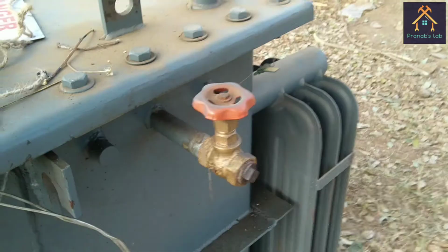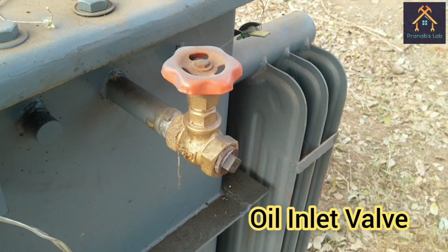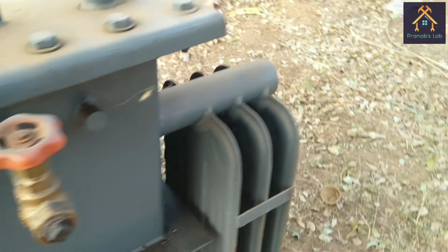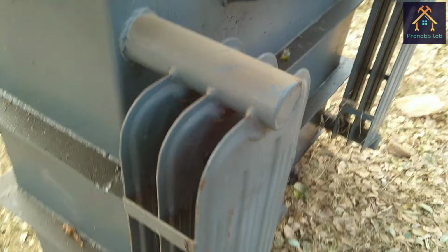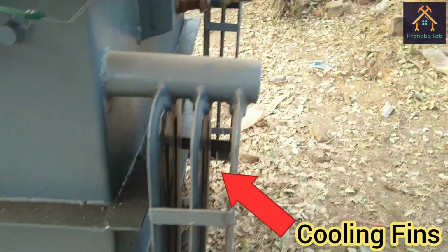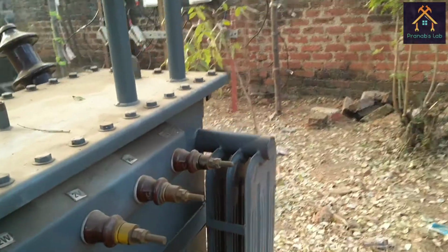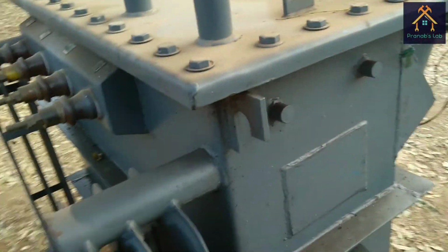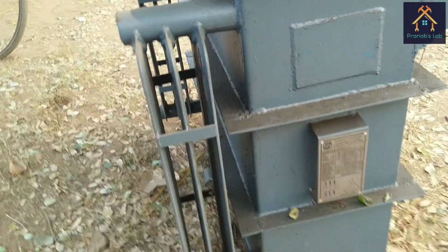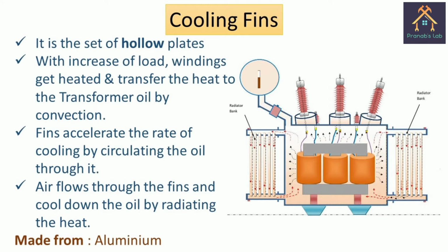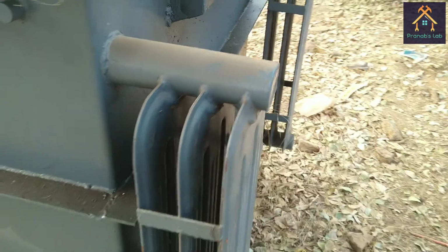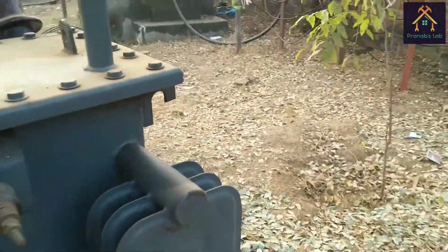Now you can see this is the transformer oil inlet valve provided on the top level of the transformer main tank. Now you can see the blade looking objects, that are called the cooling fins. It is also called the radiator of the transformer. It is mainly a hollow plate through which oil can easily flow. When the load increases, the heat produced inside the core also increases. Then the oil inside the transformer helps to radiate the heat by flowing through these fins. The surrounding air cools down the oil by flowing through the gaps of the fins. It actually increases the effective area of the tank.